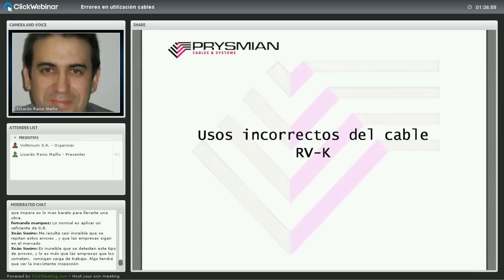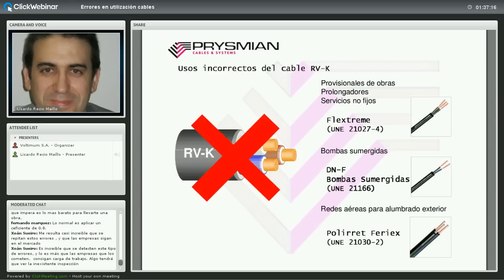Errores en la elección del tipo de cable: usos incorrectos del cable tipo RVK. El RVK es de fácil disponibilidad y tiene sensación de robustez y flexibilidad, pero no vale para todas las aplicaciones. No vale para provisionales de obras, ni para prolongadores, ni para servicios no fijos (es decir, cables que se mueven en tensión o de quita y pon). Un servicio fijo es un cable instalado bajo tubo, canal protectora, bandeja o grapado; un servicio móvil es un cable que se mueve o se retira.